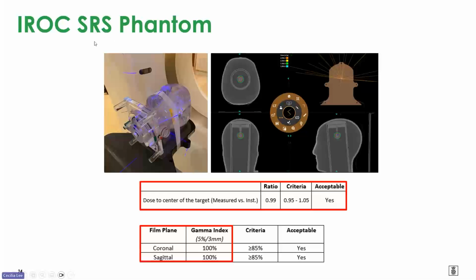And then I also ordered the IROC SRS phantom. It's a third-party phantom, and the result was pretty good. What we reported versus what they read: there is a little TLD inside, and it was within 1%. There was also a film inside, so they did a 2D analysis, but their criteria is pretty loose, 5% and 3 millimeters. So it was all 100%, which I expected.